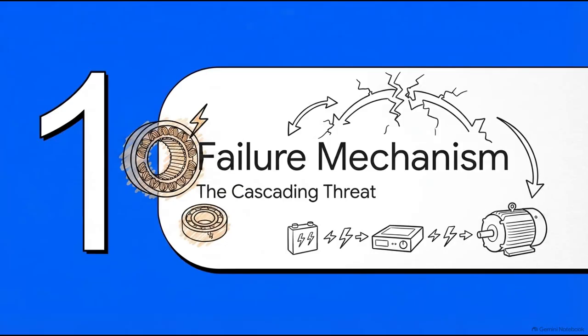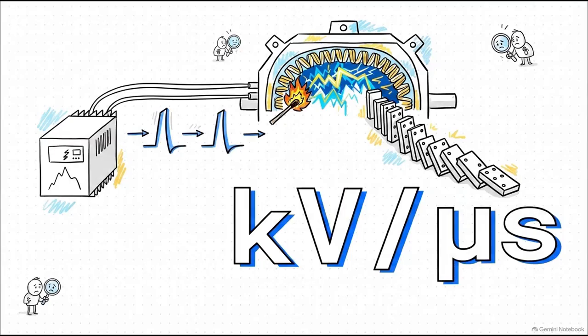Section 1. The cascading failure mechanism. To really fix a problem, you first have to understand the physical disease that's destroying the motor from the inside out, right? And it all starts with this invisible threat, high-frequency electrical stress sparking a massive domino effect. 10 kilovolts per microsecond? That is incredibly fast and absolutely wild. When the EV's inverter does its high-frequency switching to pulse power to the motor, it doesn't just send a clean signal. It creates these violent voltage change rates up to 10 kilovolts per microsecond. Literally, this is the match that lights the fire.